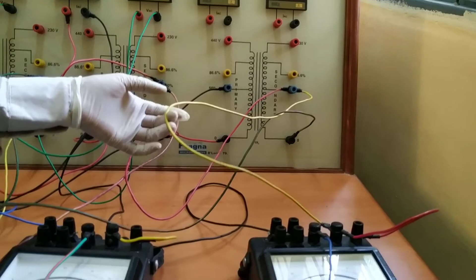Now let us see the delta connection of the resistive load bank. We have R phase with 2 terminals, Y phase with 2 terminals, and B phase with 2 terminals. Again here we go for end-to-end connectivity. One end of R goes to one end of Y, then the other end of Y goes to the first end of blue, and the second end of blue comes to the first end of R. This is how it is connected end to end to form the delta connection.